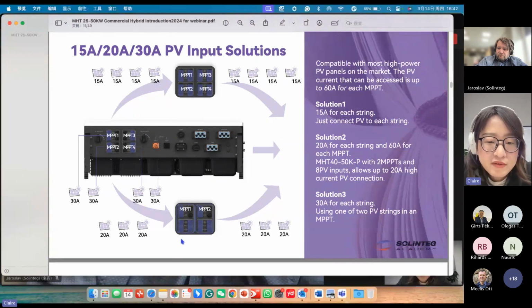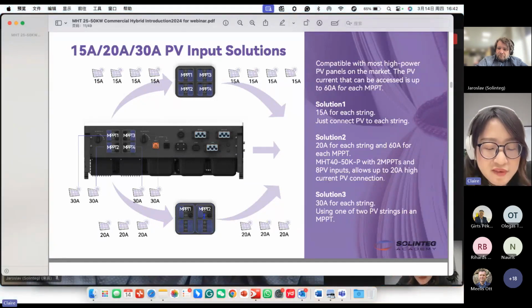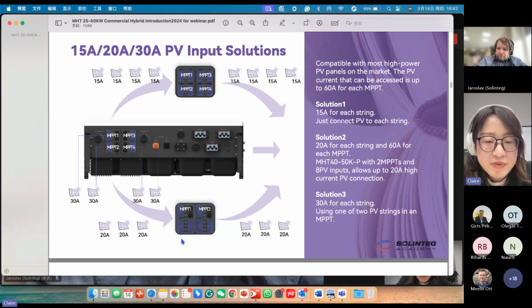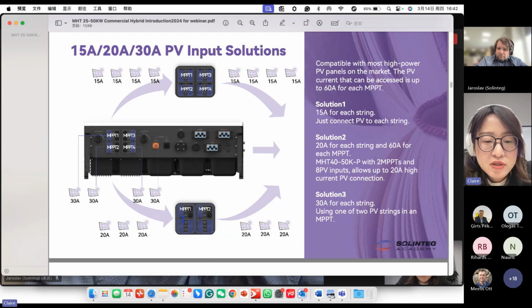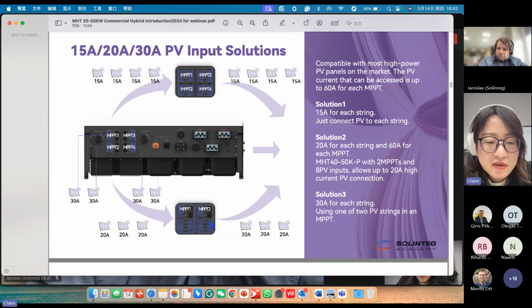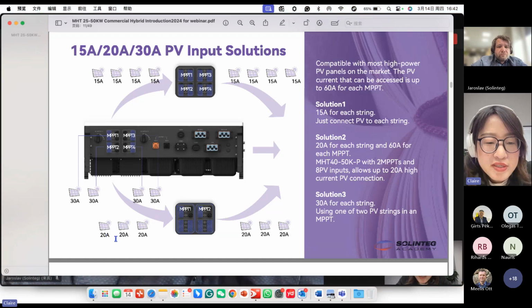Like this one. This is another version of the inverter with only 2 MPPTs, and each MPPT has 4 PV strings. That makes the whole MPPT have a maximum input current up to 60 amperes. So we can connect 3 PV strings to each MPPT. This makes it so we can connect a total of 6 PV strings in this inverter, and the maximum input current for each PV string is 20 amperes.